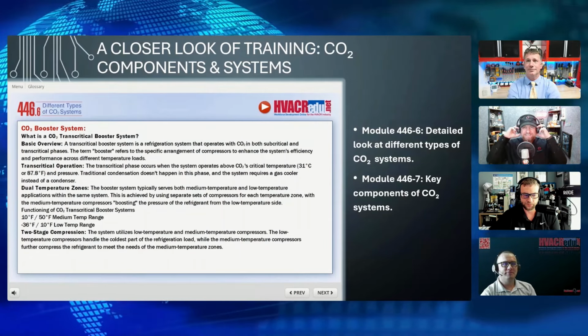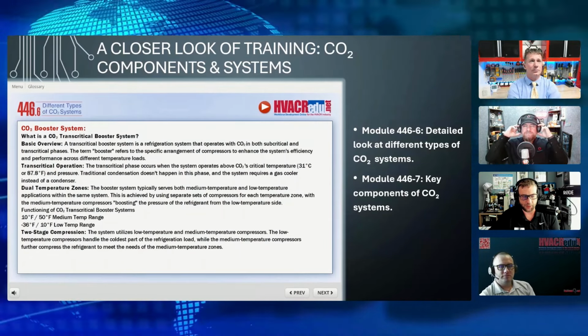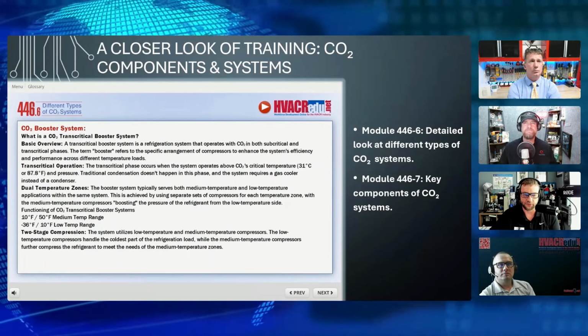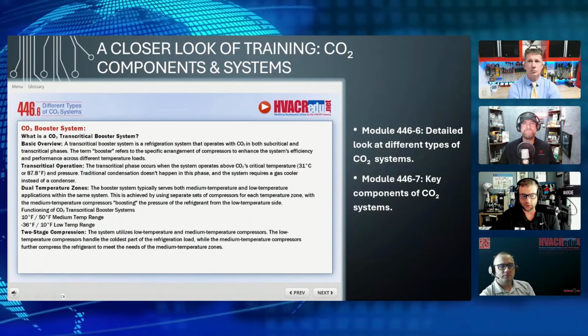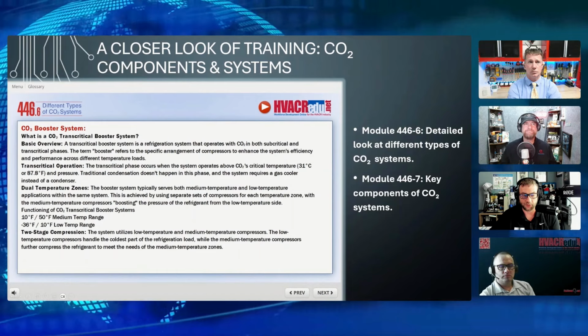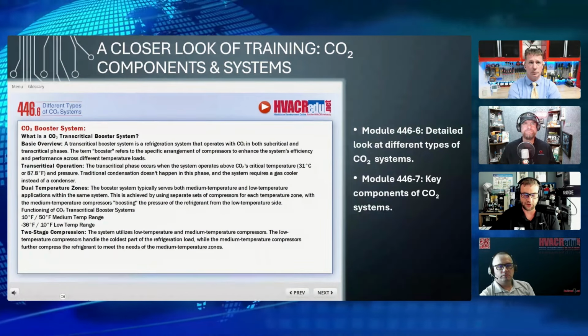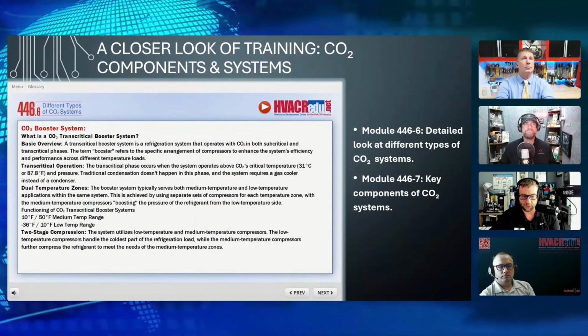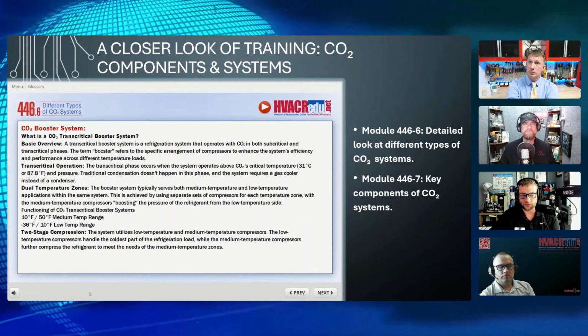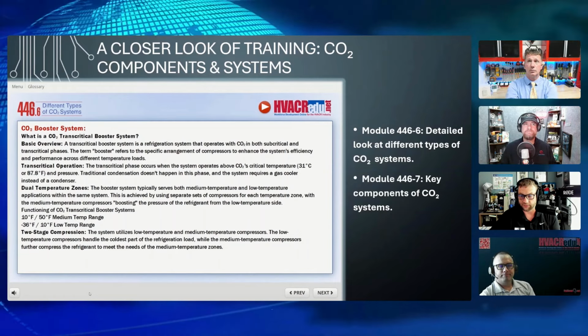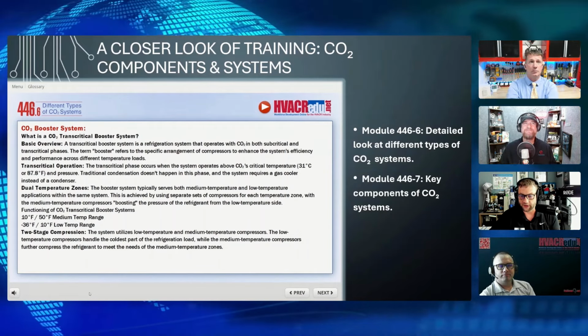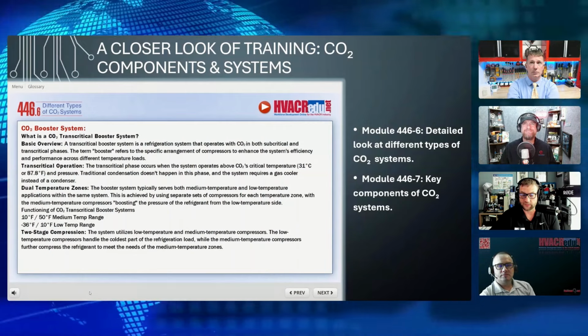Yeah, 100%. So I break down the ranges of what a medium temp and low temp booster could do: as high on the medium temp as 50, as low as maybe about 10 degrees. And the same with the low temp: we can go as low as negative 36 to as high as about 10 degrees saturated suction temp.